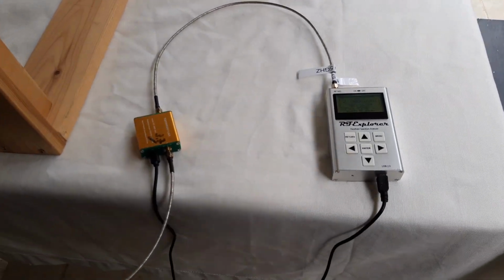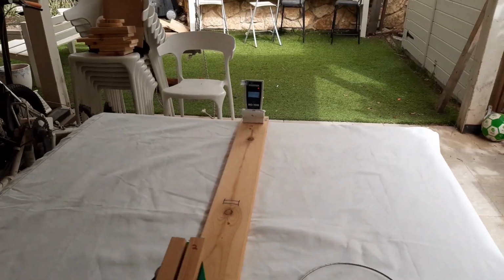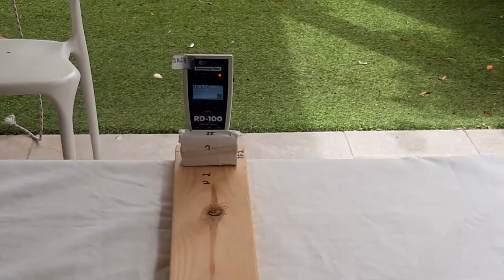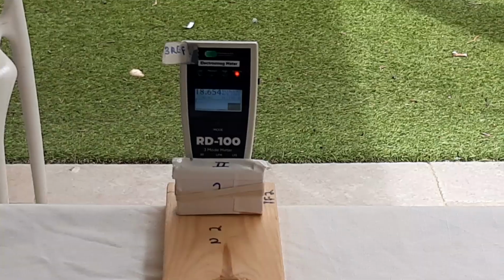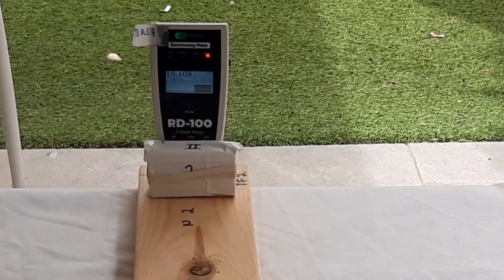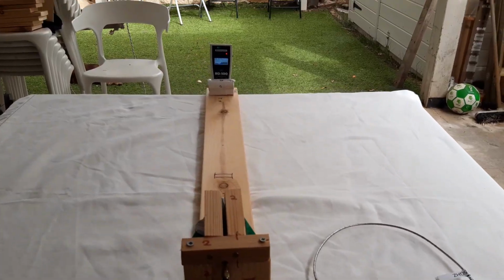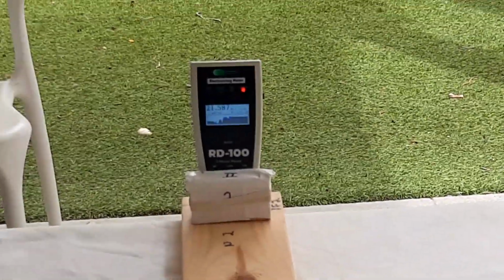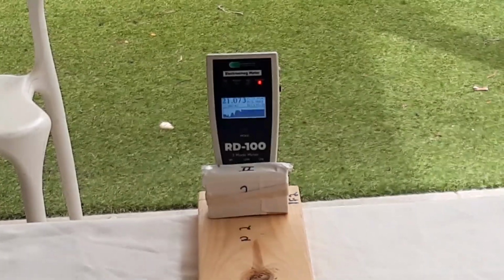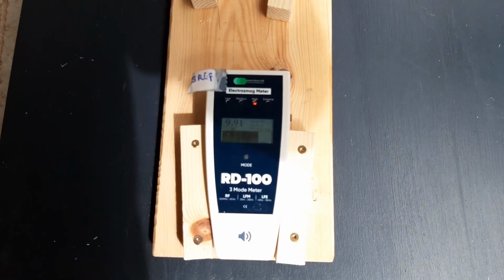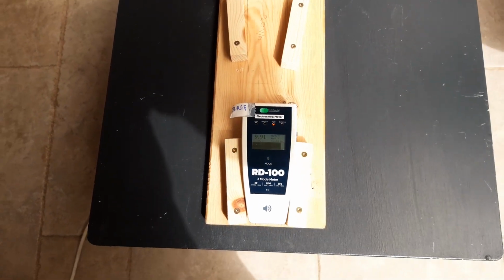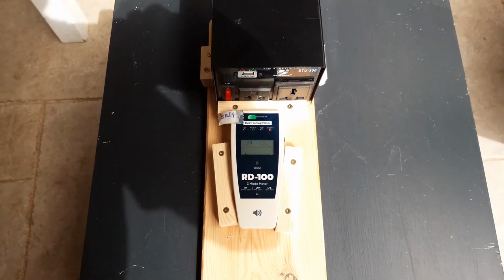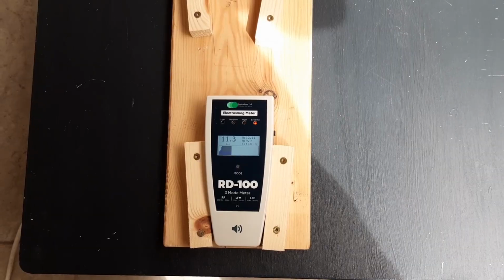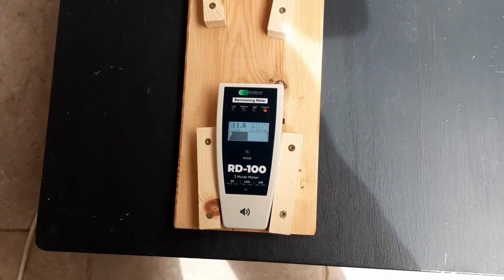And now for the test itself, starting with the radiation and transmission, and I'm measuring the RF at the point that the meter is located at. I got about 19.1 milliwatt per square meter. And now I'm doing the same for the unit under testing, getting 21.5, something like that, 21.0 milliwatt per square meter. I'm doing the same for the low frequency magnetic and low frequency electric. I'm using the reference in order to test the low frequency magnetic, getting 9.9 milligauss, and the low frequency electric getting around 23 volt per meter, and redoing it for the unit under testing, getting 11.8 milligauss.